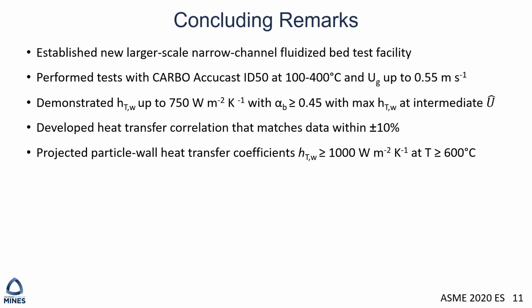We have demonstrated particle-to-wall heat transfer coefficients up to 750 watts per meter squared Kelvin with particle volume fractions greater than 45%. We developed a new heat transfer correlation that matches data within plus or minus 10%. Using the correlation, we projected particle wall heat transfer coefficients in excess of 1000 watts per meter squared Kelvin at conditions relevant for particle SCO2 heat exchangers.